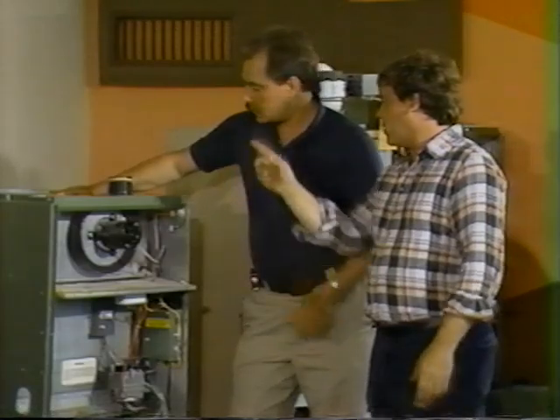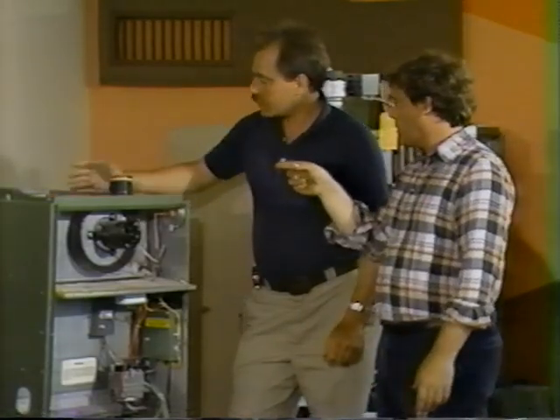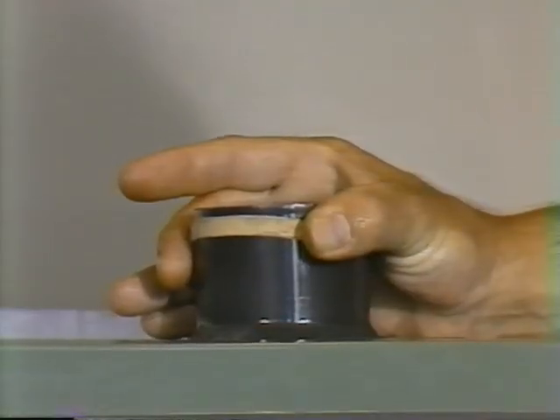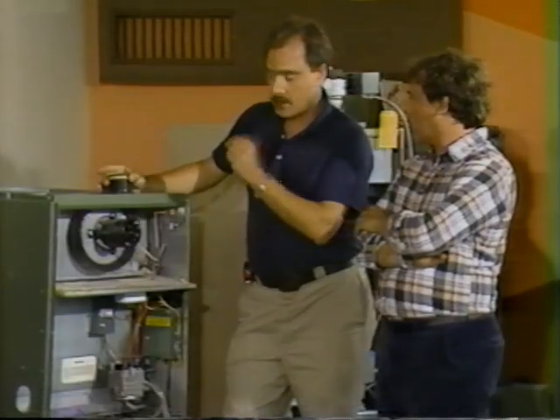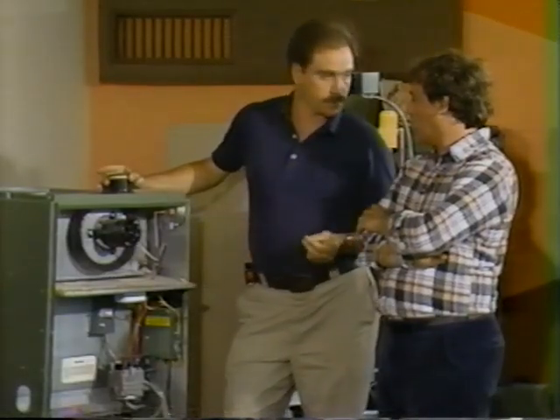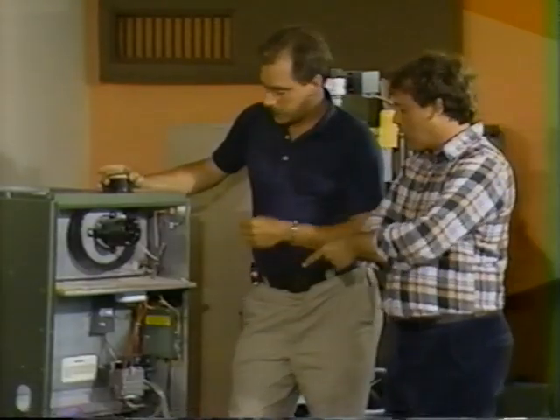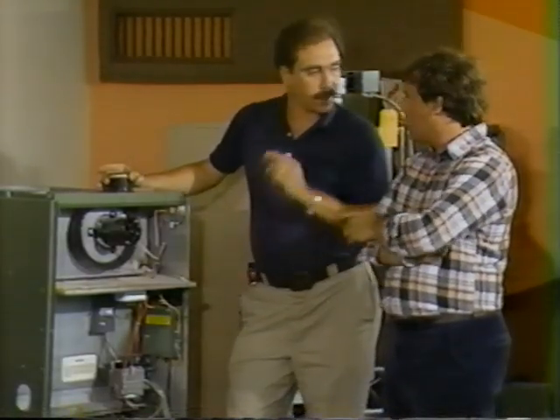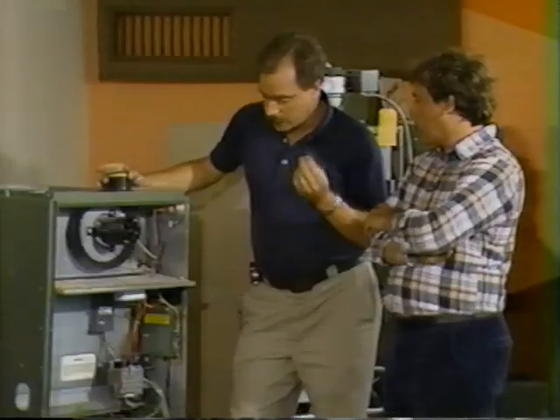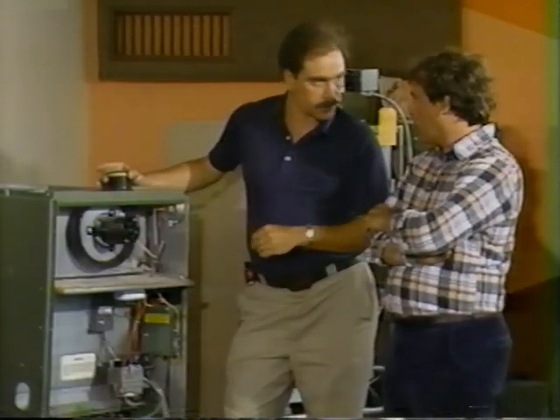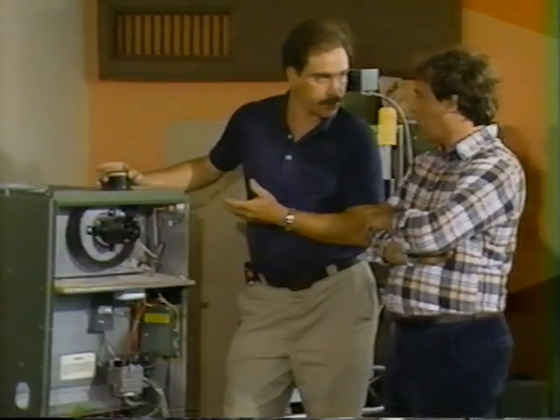Looking at the small outlet, does this thing need a chimney still? It doesn't. It's possible, because the flue gases are now cool enough, to vent them through a small pipe, and you can actually credit the cost of this unit with the fact that you no longer have to build a chimney. Okay, does this one still use room air? It does, and in an energy-conserving building, you would have to bring exterior air to the unit to ensure that it would have adequate combustion air.